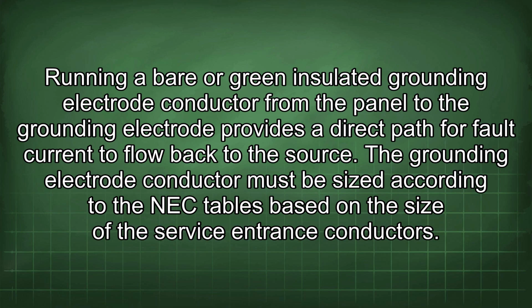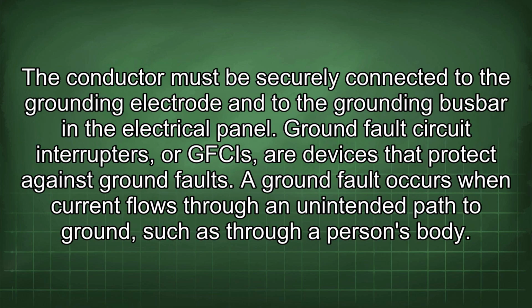The grounding electrode conductor must be sized according to the NEC tables based on the size of the service entrance conductors. The conductor must be securely connected to the grounding electrode and to the grounding busbar in the electrical panel.